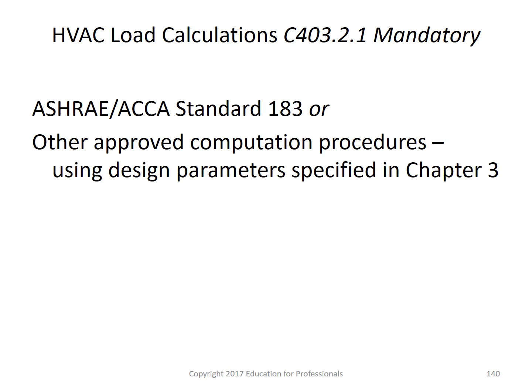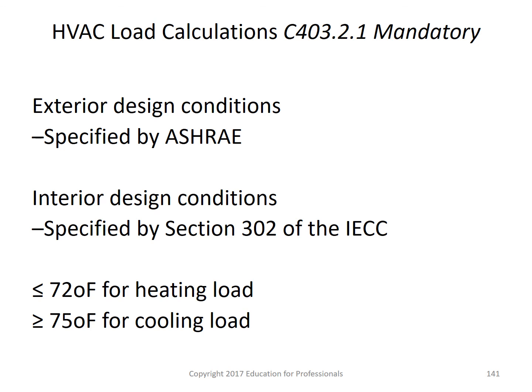Here we have taken into consideration the exterior design conditions, which are also specified by ASHRAE, and the interior design conditions, which are specified by the IECC. In general, they're less than or equal to 72 for the heating load or 75 for the cooling load. Here are some of the HVAC load calculations and who specifies them, both ASHRAE and the IECC.